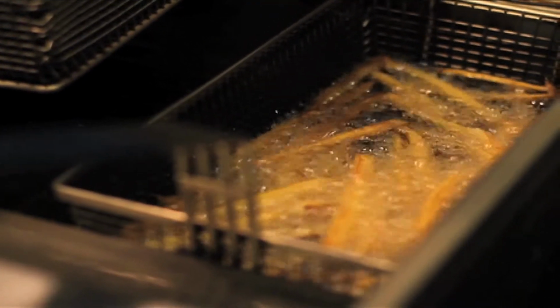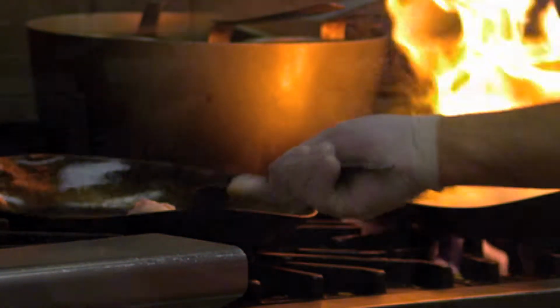People are no longer using animal fats, with the use of animal fats being phased out for vegetable oils. The dry chemical systems are no longer effective. The dry chemical systems are the systems of the past. If you have a dry chemical system, it must be upgraded to a wet chemical system. The wet chemical system is a UL 300 system. There are wet chemical systems that are non-UL 300, so you must upgrade those also. The fires are much hotter, and dry chemical will not put that kind of fire out. We have designed a UL 300 system, which is a wet chemical that will suppress the fires much better than the dry chemical.